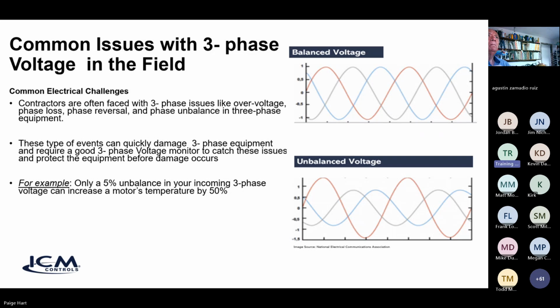So what are some of the common issues that can occur when you have three-phase voltage? Well, you can only imagine, you've got three individual voltages that are offset by 120 degrees, and those things all have to be well balanced. If you have things that are out of balance, or if God forbid you lose a phase, then that throws the whole thing off and your motor can really draw a lot of current. So a phase loss is critical, and it can create a very big problem very quickly for your motor. Contractors are often faced with these issues: over and under voltage, phase loss, phase reversal, and unbalance, and those things can very quickly damage the motor.